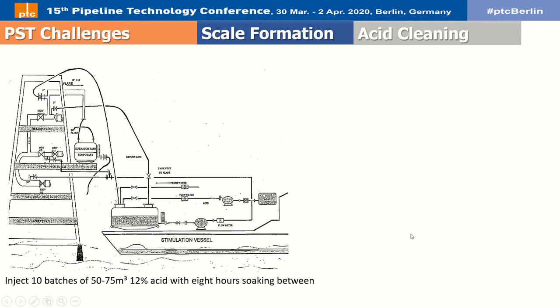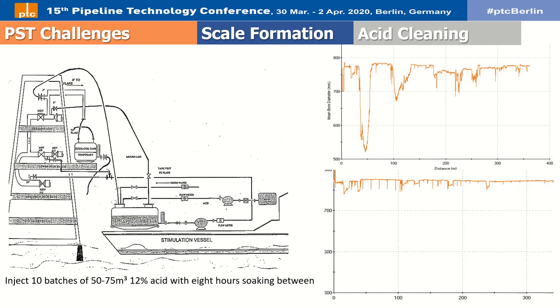To dissolve the scale, a massive acid cleaning operation was conducted by injection of inhibited hydrochloric acid between pigs using the pistoning technique, followed by acid withdrawal by depressurizing and subsequent neutralization by soda ash.